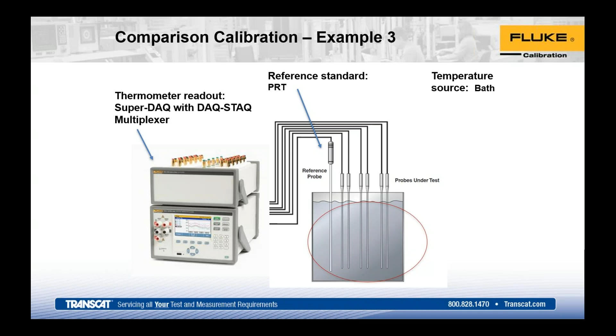And I brought this picture back up just to show you here. If we go between these two, you can see, ideally here, we've got the 4 sensors that we're testing and then the reference in the center. This was just to show you throughput. But if we were actually calibrating these sensors, we would probably have the reference in the center and then a circle of these test devices, basically not side by side going across the bath. So again, we're trying to reduce the space that we're utilizing to improve upon the uniformity spec. So that's just a little tip there.